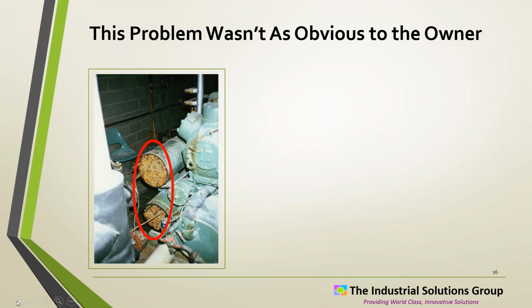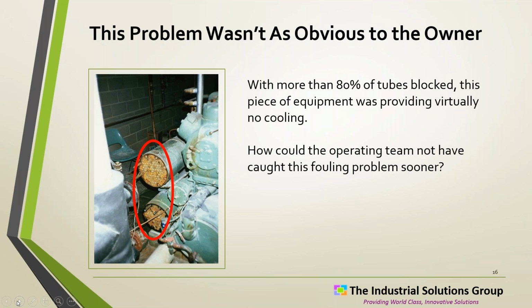But some problems aren't as obvious to owners. This is that chiller they were trying to keep online with a fan. And it's true that if a piece of equipment starts getting hot, it'll drop offline. But the other thing that'll drop it offline quickly is, there's supposed to be about 100 tubes that you can see, and you can only see openings in a few of these tubes. They're clogged solid because of a poor water treatment program. 80%, maybe even 90% of these tubes are blocked.